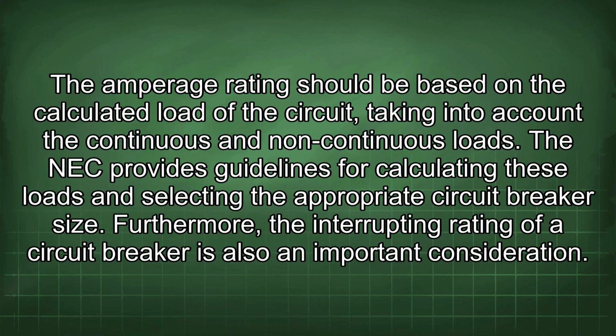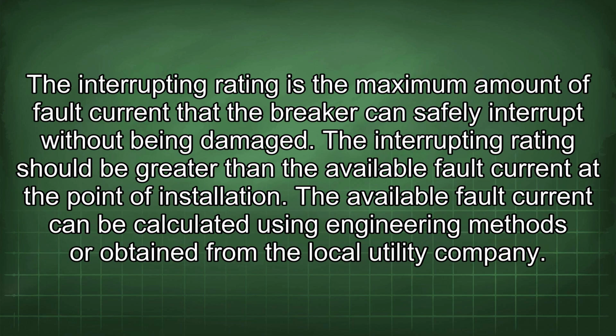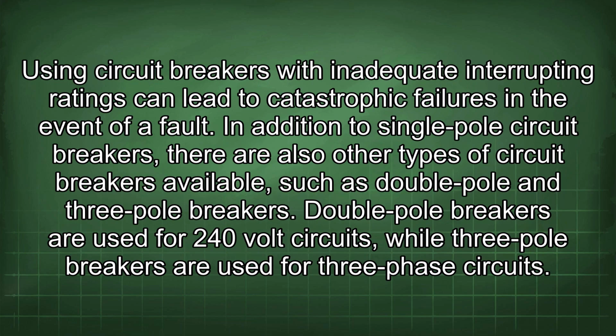Furthermore, the interrupting rating of a circuit breaker is also an important consideration. The interrupting rating is the maximum amount of fault current that the breaker can safely interrupt without being damaged. The interrupting rating should be greater than the available fault current at the point of installation. The available fault current can be calculated using engineering methods or obtained from the local utility company. Using circuit breakers with inadequate interrupting ratings can lead to catastrophic failures in the event of a fault.